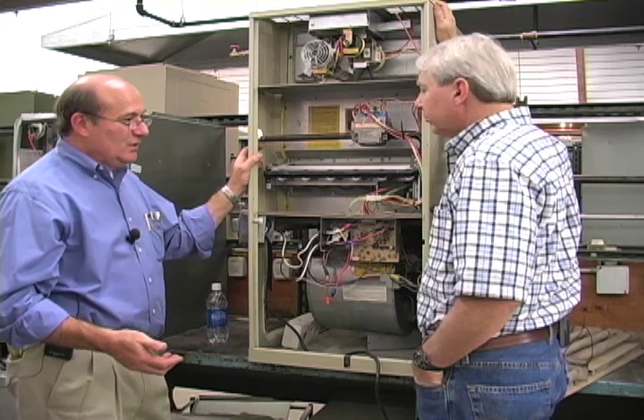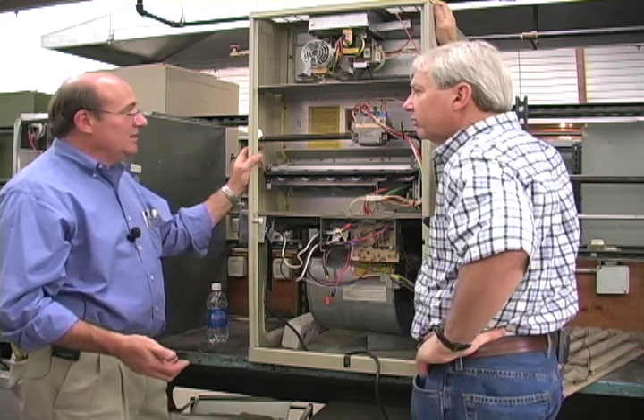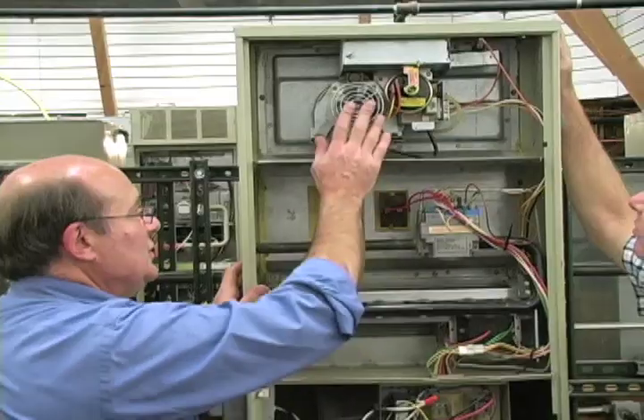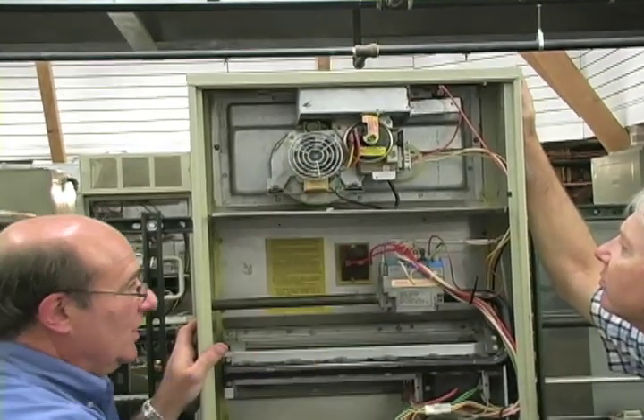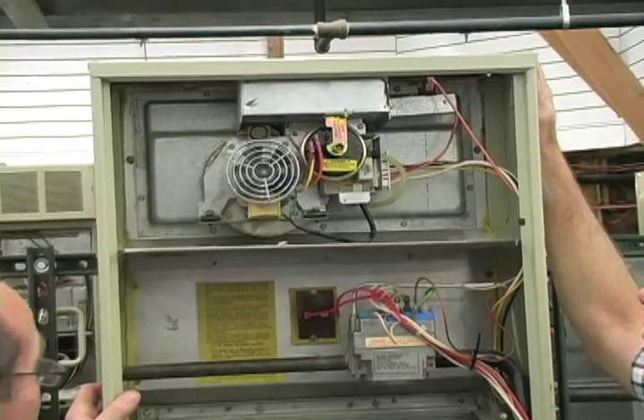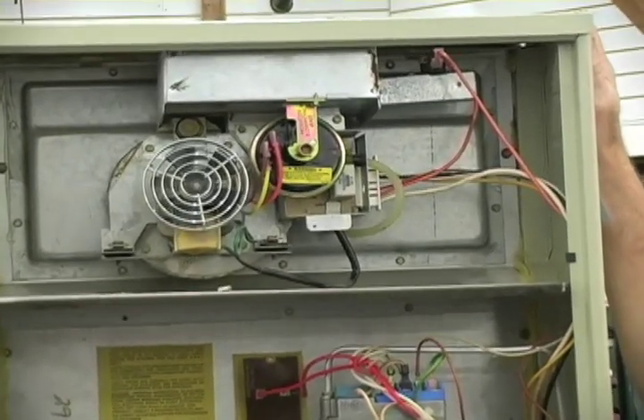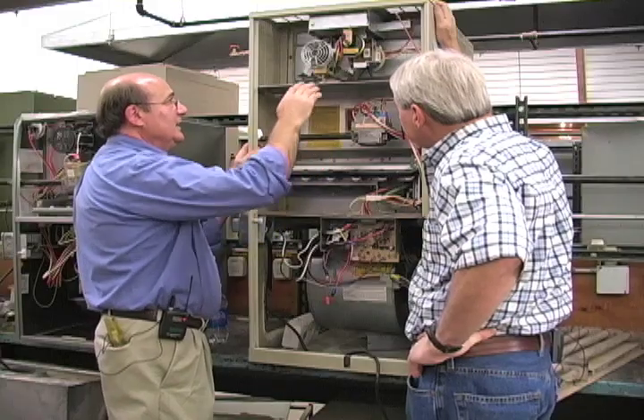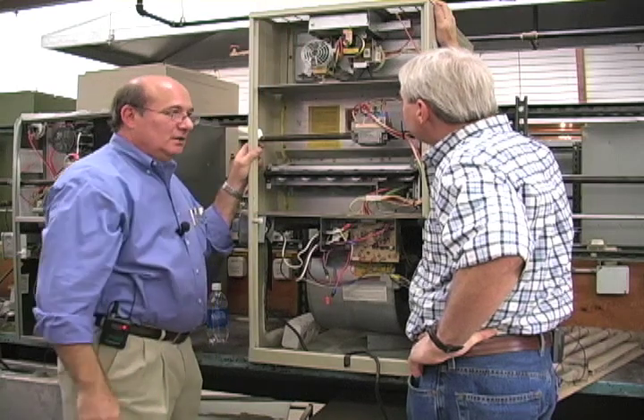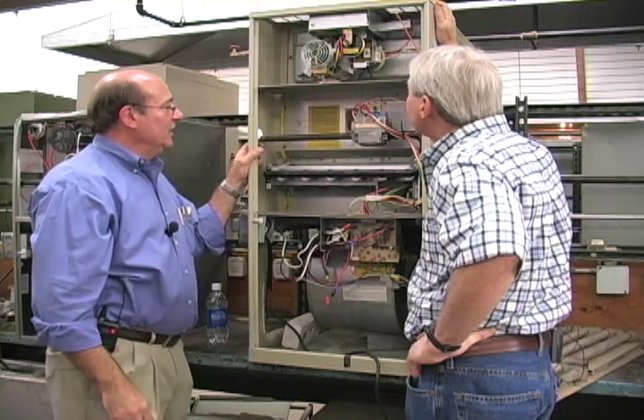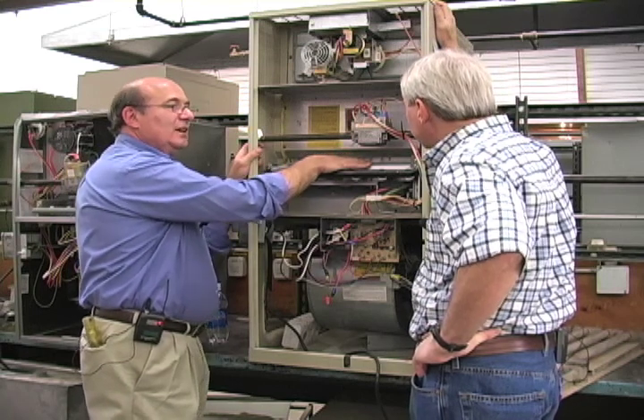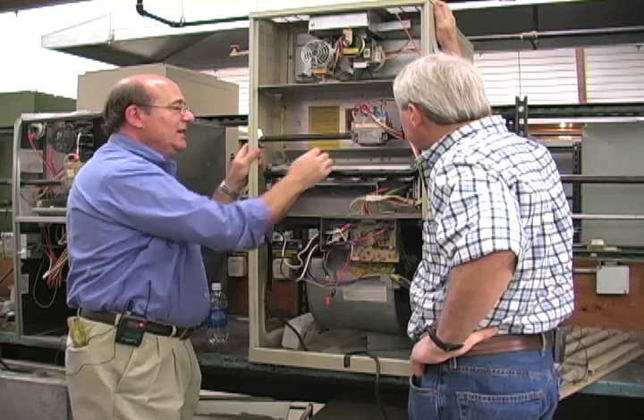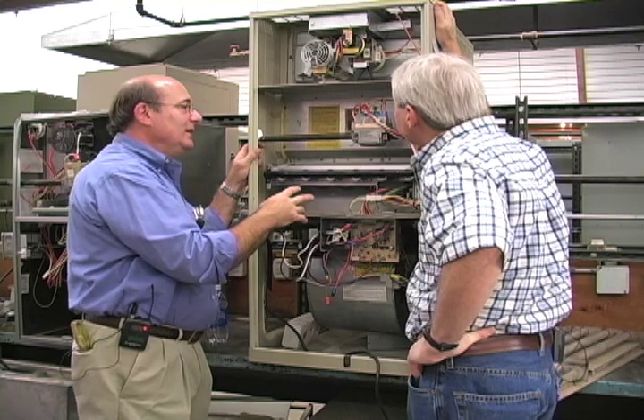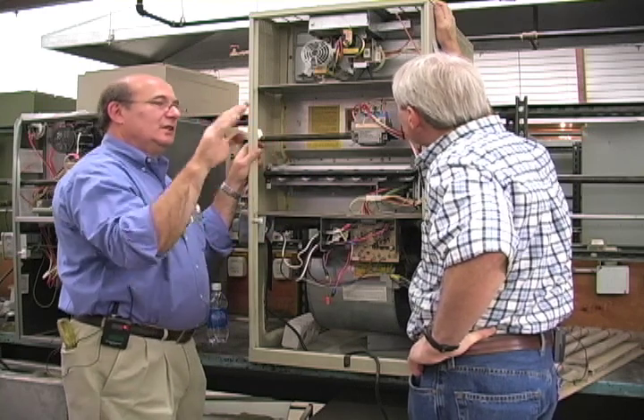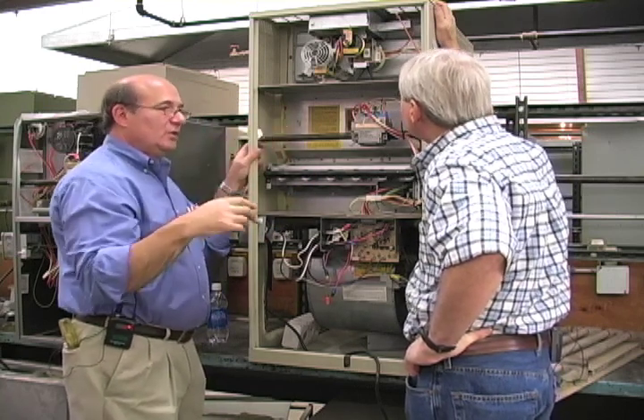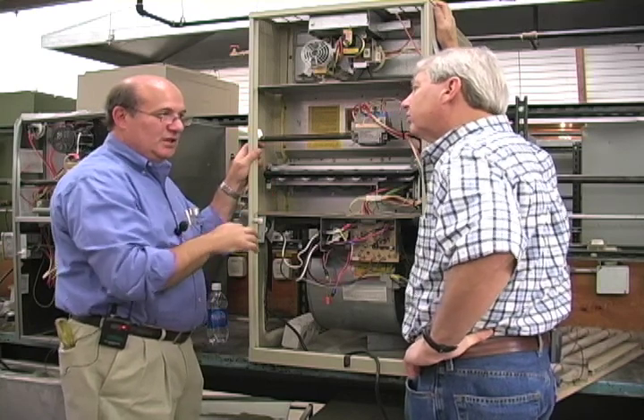And primarily, the first feature that we see on it that everyone becomes immediately aware of is the combustion blower motor, or inducer blower motor. This particular furnace draws air through the heat exchanger and exhausts it up through the top under a very slight positive pressure. So the combustion chamber itself is drawn down to a negative pressure, and that draws the flame into the compartment. And then the flame can be delivered in a serpentine fashion or through a series of tubes, and I'll show you some of those later.